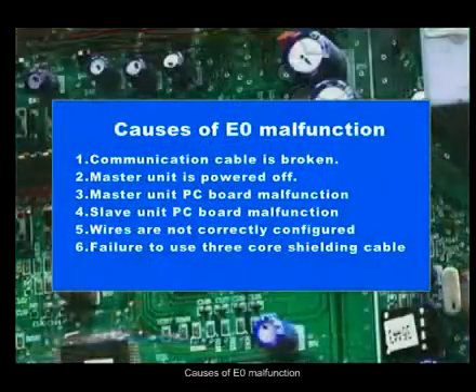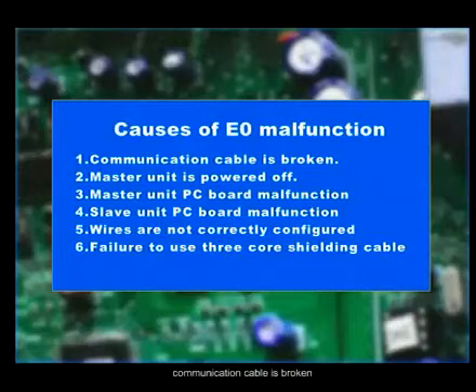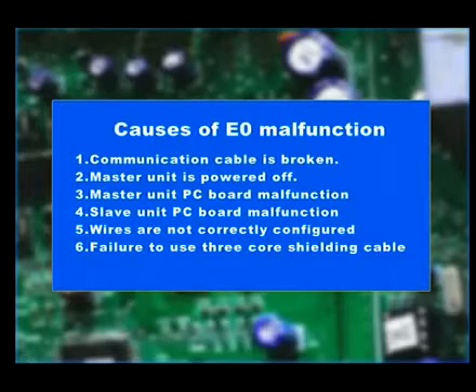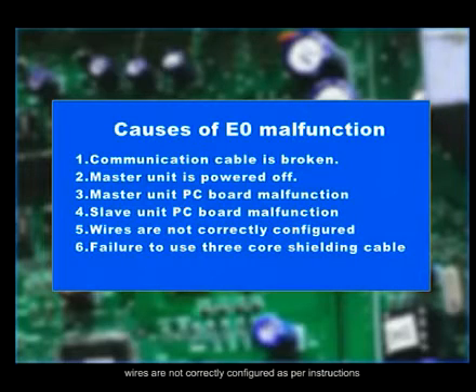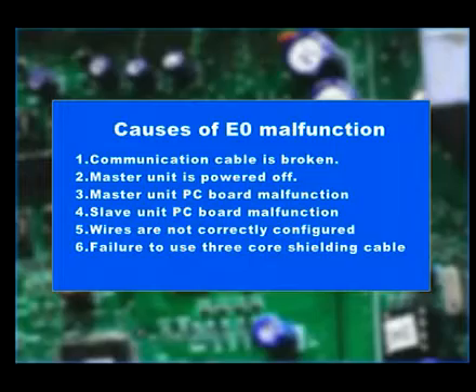Cause of E0 malfunction. Communication cable is broken. Master unit is powered off. Master unit PC board malfunction. Slave unit PC board malfunction. Wires are not correctly configured as per instructions. Failure to use 3 core shielding cable.